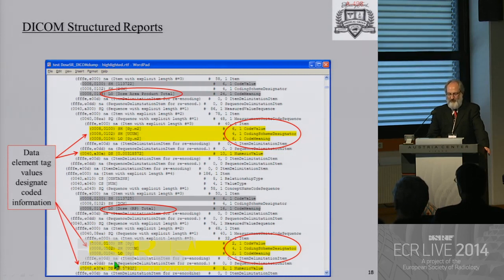This one is the total dose at the reference point. So these tags are identical. They're just the code meanings. You have to look at what the code meaning is. This is now gray, not like DAP, gray meters squared. This is just gray because it's a total dose.